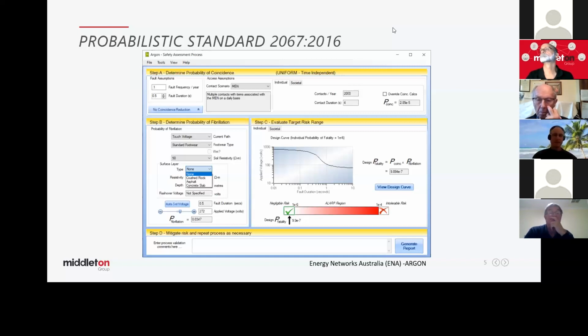Just another comment too in regard to your distribution pad mounts that you suggested that people might go back and common bond up the earthing systems. It'd be nice if that happened, but it doesn't. Generally, when an ASP installed an earthing system, they'll never go back to it, and we don't have the resources as a utility to go around common bonding up earthing systems. So the initial design needs to be complete before it gets approval. And also, the MEN may never be established given new installation practices of non-conductive water pipe and the like. So it needs to be compliant to start with.